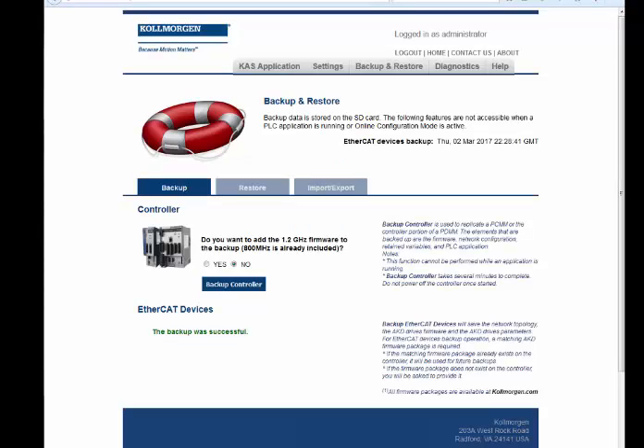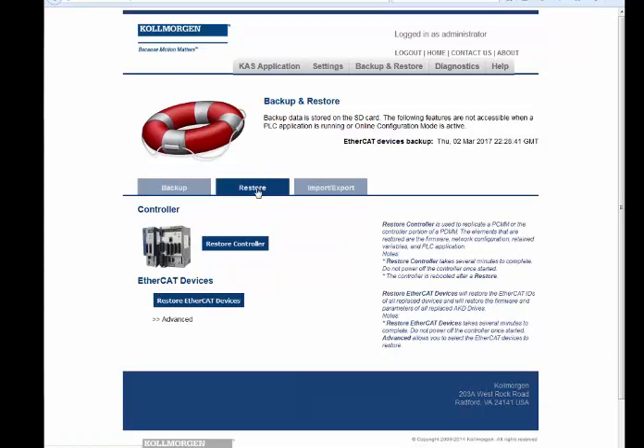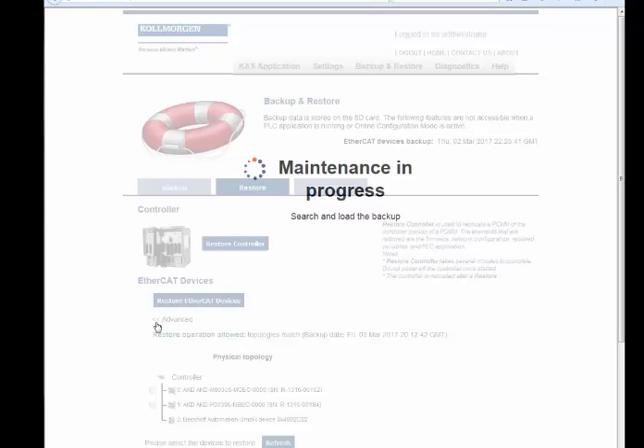In the Restore tab, both the backup controller and EtherCAT devices can be transferred from the SD card to another controller. Restoring the controller takes several minutes to complete. Do not power off the controller once started. The controller will reboot at the end of the restore. Advanced allows you to specifically select the EtherCAT devices to restore.